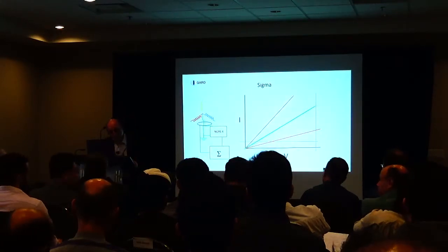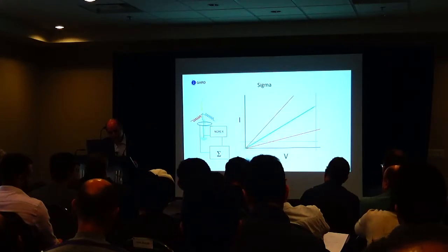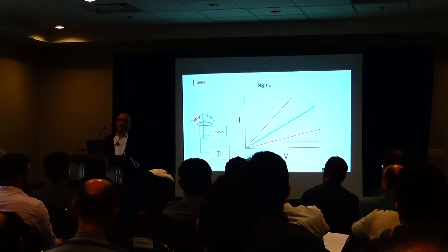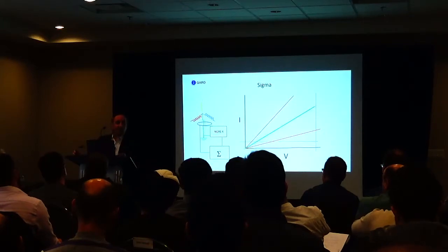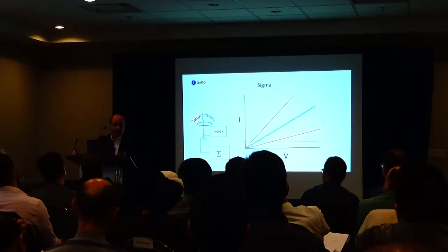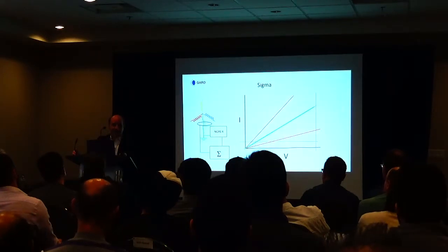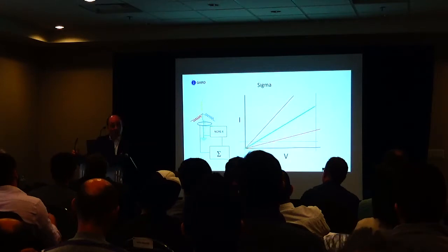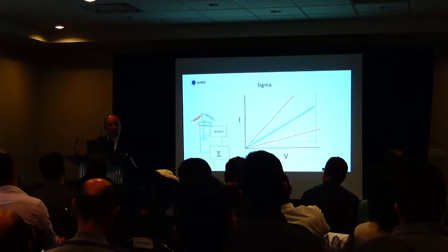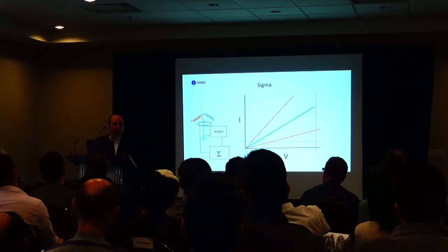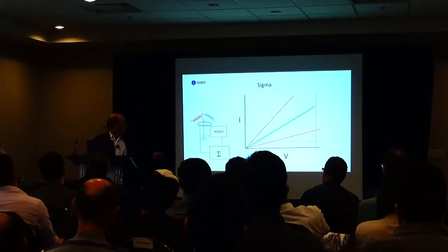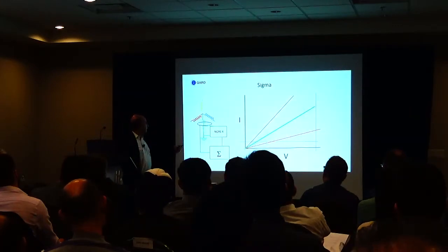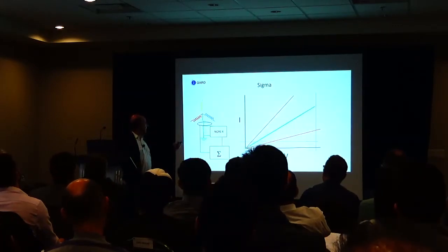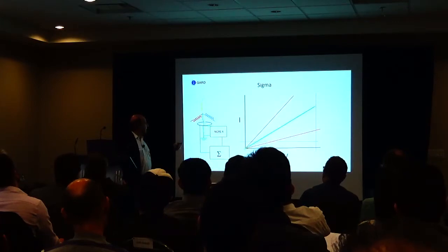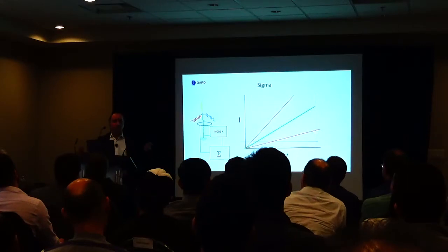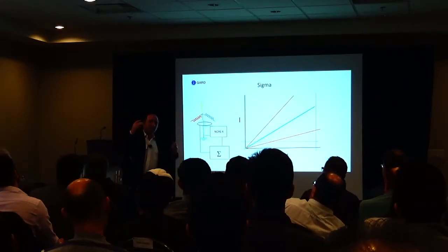But it depends on the manufacturing of this and the quality of it. In my resistors, we rarely have a problem with what we manufacture here. Typically what happens is, if you're in an area with a highly corrosive environment, near the ocean, it's possible to get deterioration of the connections, of the cable, of the wire. I'll give you an example. See this point right here? This point monitors the integrity of the connection from here, and you can move that point right to the transformer neutral. So you're going to monitor the entire length of that neutral cable as well.